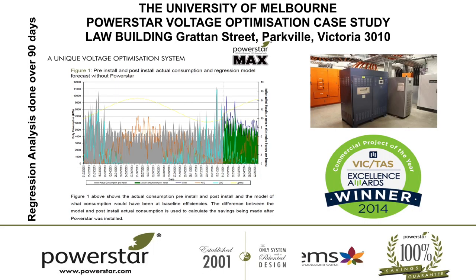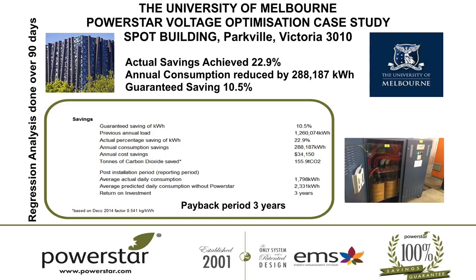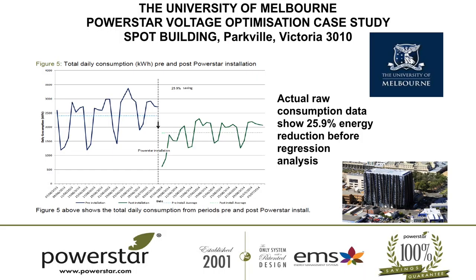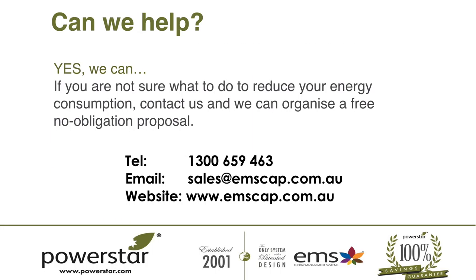We're conservative in what we say to clients because we want the actual number to be higher, with a payback period under four years verified through IPMVP regression analysis. That's a 1,150 kVA dynamic unit installed at the University of Melbourne. Also, the SPOT building in Carlton Parkville achieved 23% energy saving — the client had VSDs, LED lighting, compact fluoros, and high-frequency fluoros, and asked what we could save. We told them 10.5% and actually achieved 23%, because their average voltage was 249 volts. On the raw data it was nearly 26% energy saving. So thank you.